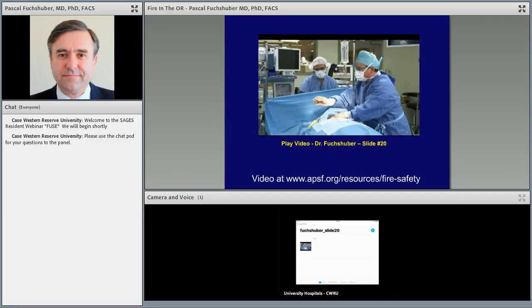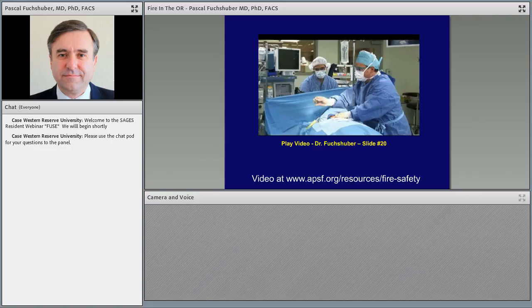So when you look at that and you say to yourself, would I be able to make this happen the way it's shown in the video? The answer probably is no. So it does require some training. And we do recommend that the hospitals and OR teams at least twice a year come together to train for a situation like that, because it really is a choreographed dance to react. And as you can see, the most important thing is to disconnect any oxygen source from the patient. So don't be afraid to rip out the ET tube, even in an anesthetized patient that's intubated. That's probably one of the first things you should do, and remove the drapes.